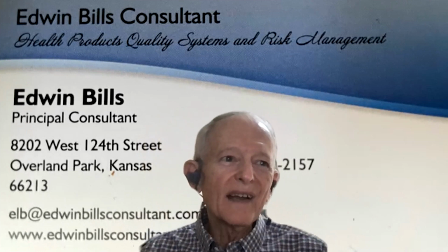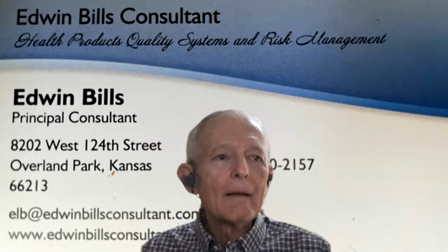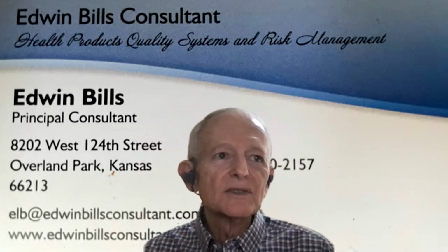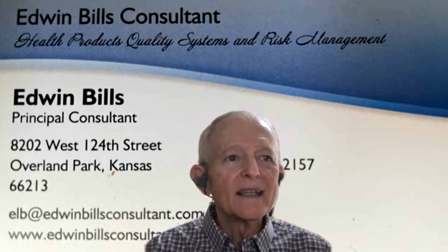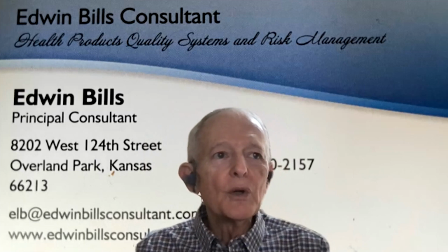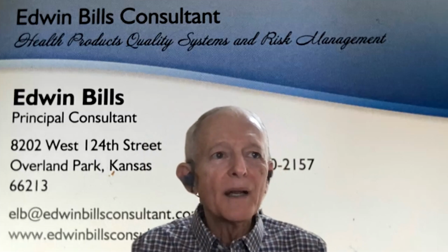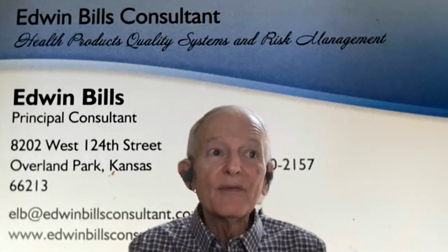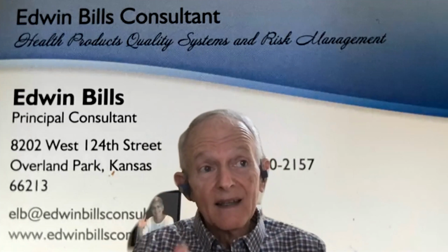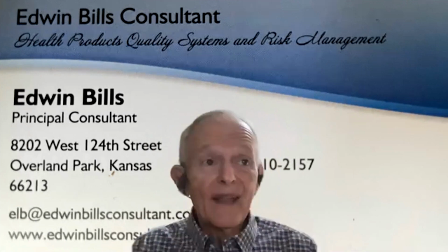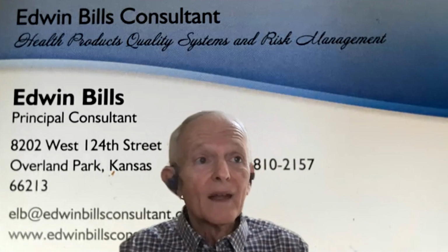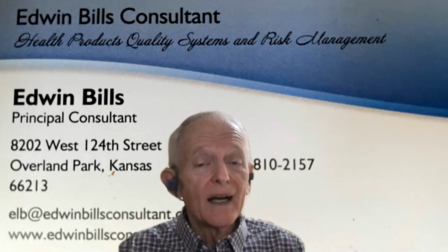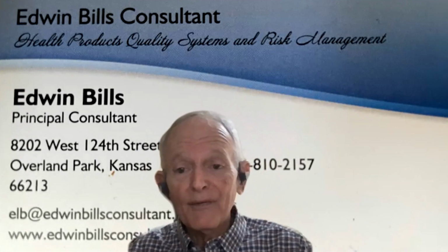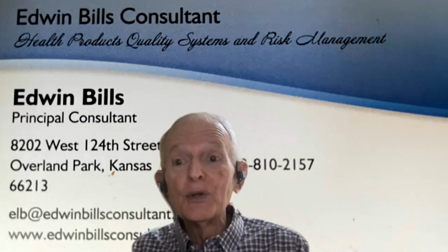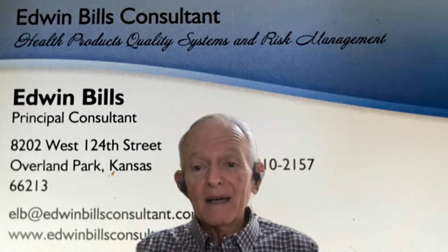So it gets kind of a funny line to walk there, but the FDA's concern more is with the people that actually change the device. So if you replace a component in a reprocessed device with a different component than the original device, then that is changing the device. And that's where you cross the line from refurbishing to actually becoming a medical device manufacturer and creating a new device. So you got to be careful there.